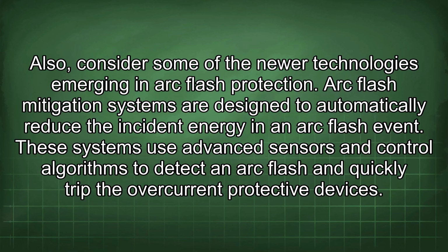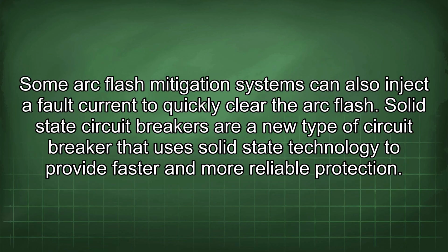Arc flash mitigation systems are designed to automatically reduce the incident energy in an arc flash event. These systems use advanced sensors and control algorithms to detect an arc flash and quickly trip the overcurrent protective devices. Some arc flash mitigation systems can also inject a fault current to quickly clear the arc flash.